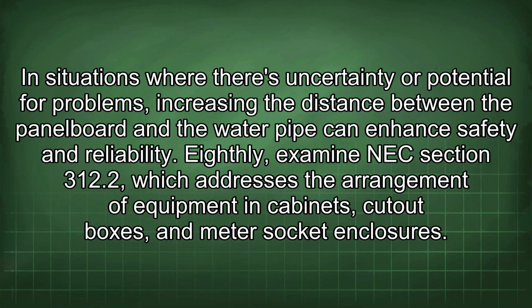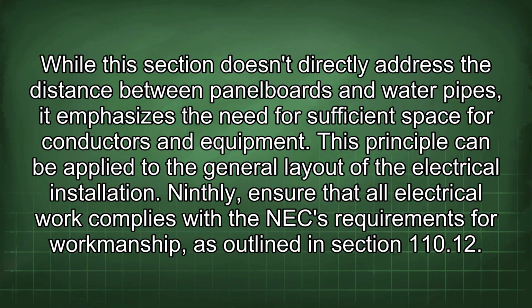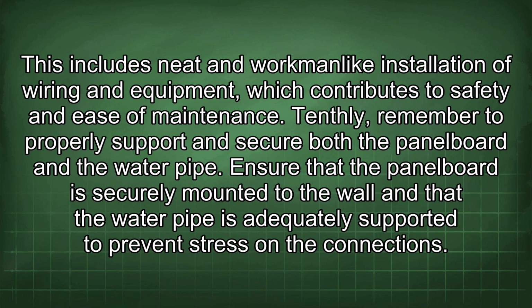Eighthly, examine NEC Section 312.2, which addresses the arrangement of equipment in cabinets, cutout boxes, and meter socket enclosures. While this section doesn't directly address the distance between panel boards and water pipes, it emphasizes the need for sufficient space for conductors and equipment. This principle can be applied to the general layout of the electrical installation. Ninthly, ensure that all electrical work complies with the NEC requirements for workmanship as outlined in Section 110.12. This includes neat and workmanlike installation of wiring and equipment, which contributes to safety and ease of maintenance.